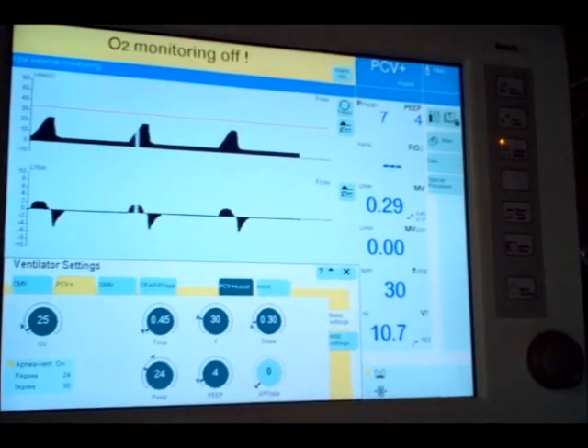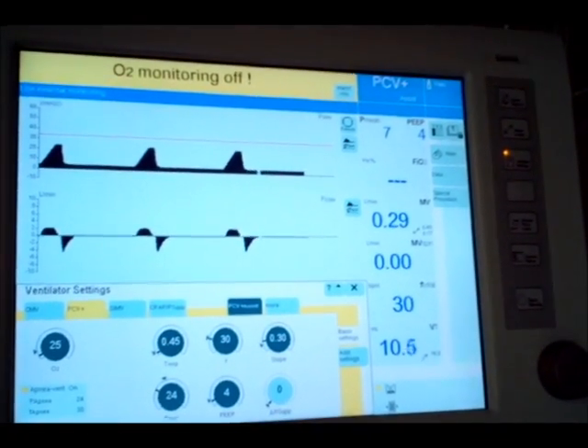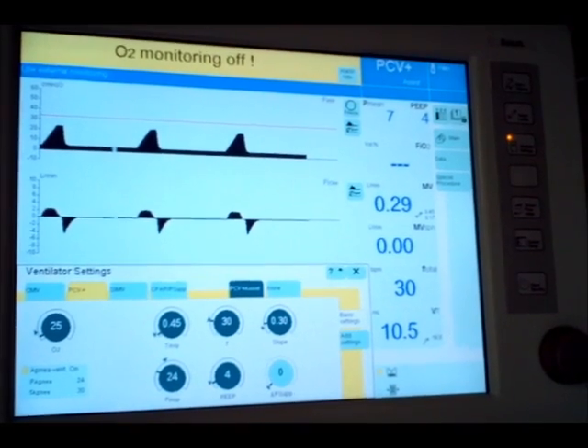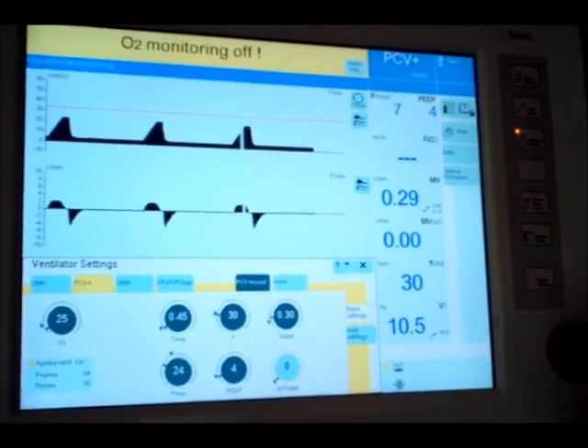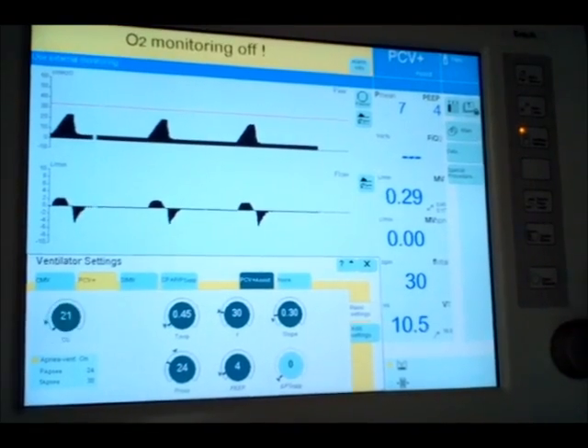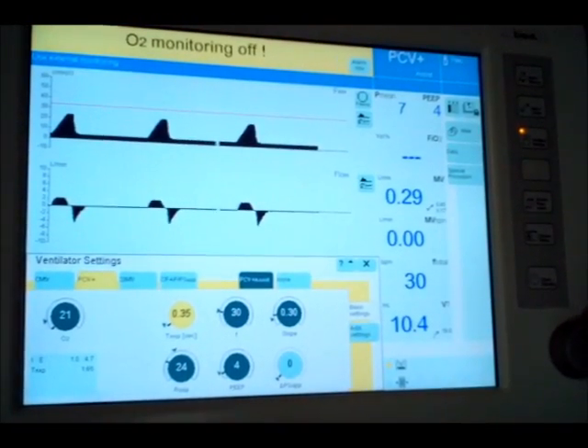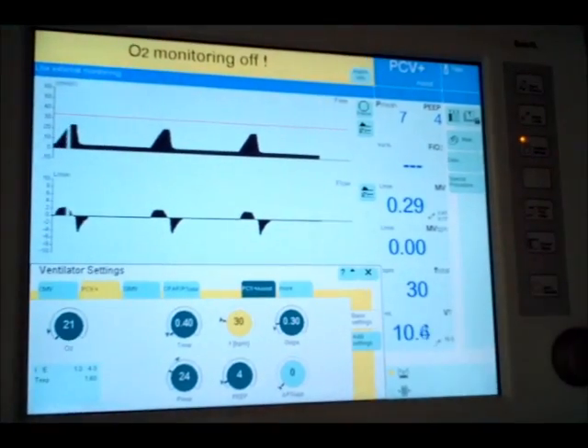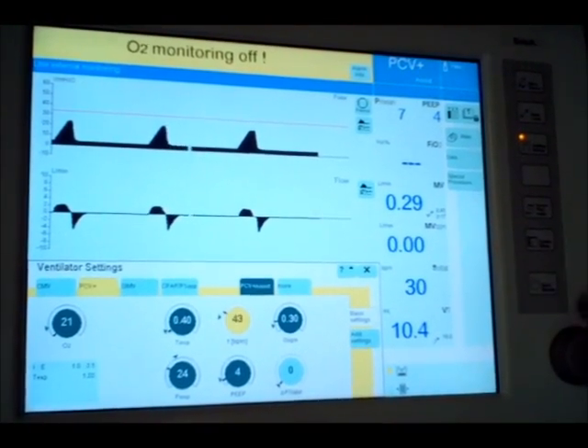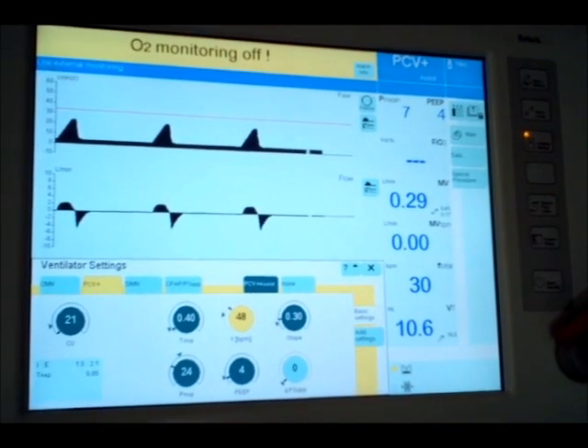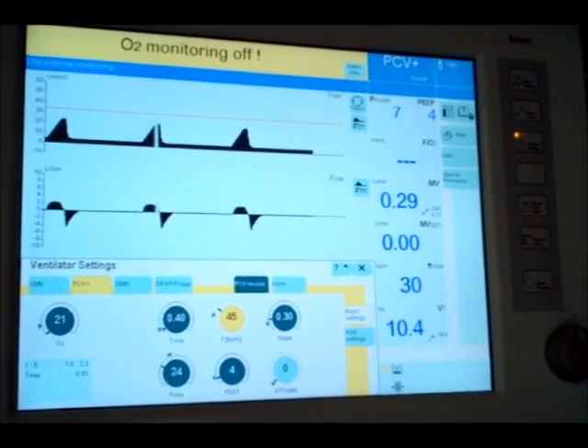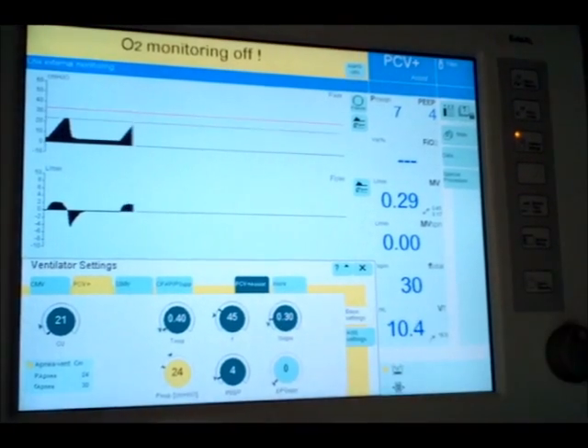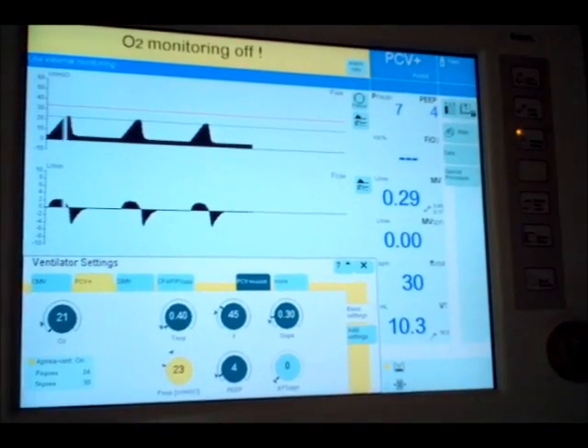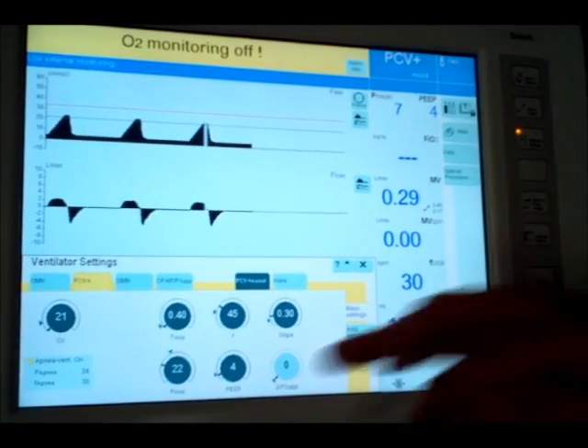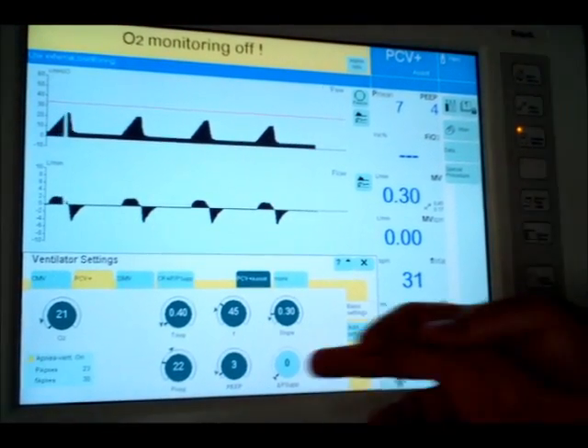All right, so PCV plus. So notice again, if you get mixed up, with PCV plus, I can set pressure support. That wasn't there when you did PCV plus assist. Okay, turn this down to 21. Inspiratory time, what is it, 0.4. Rate 45. Come back to slope, a PIP of, say, 22. PEEP of 3. Pressure support of 10.